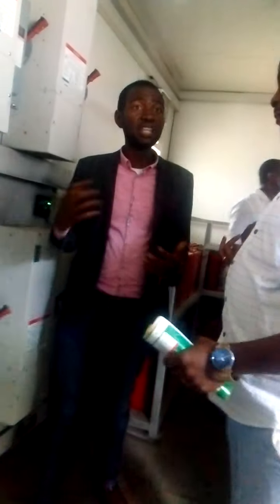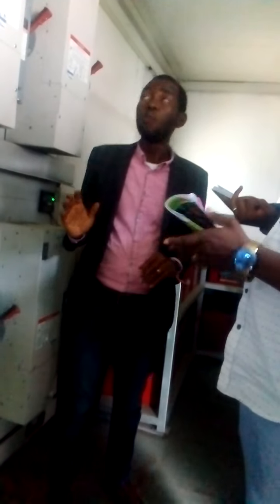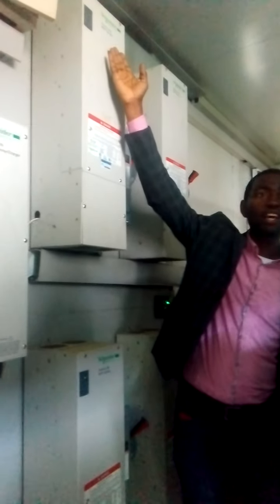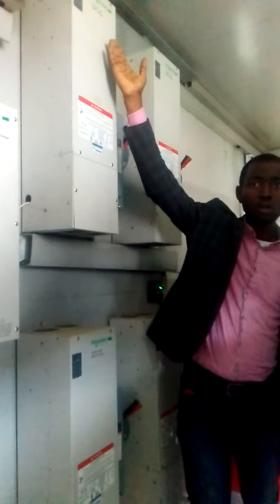Beautiful thing about this installation is the use of an MPPT charge controller. If it had been pulse width modulation, we'd have to do it voltage by voltage range. But because we have an MPPT charge controller, Schneider, which can take up to 600 volts DC and 80 amps, as the case may be.